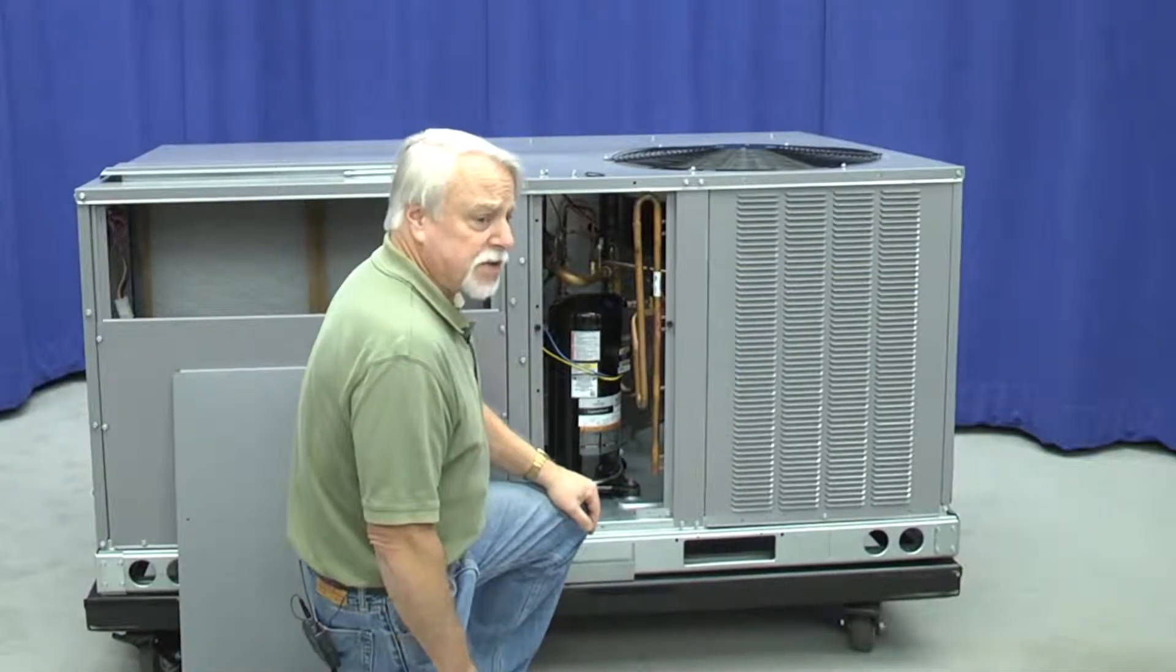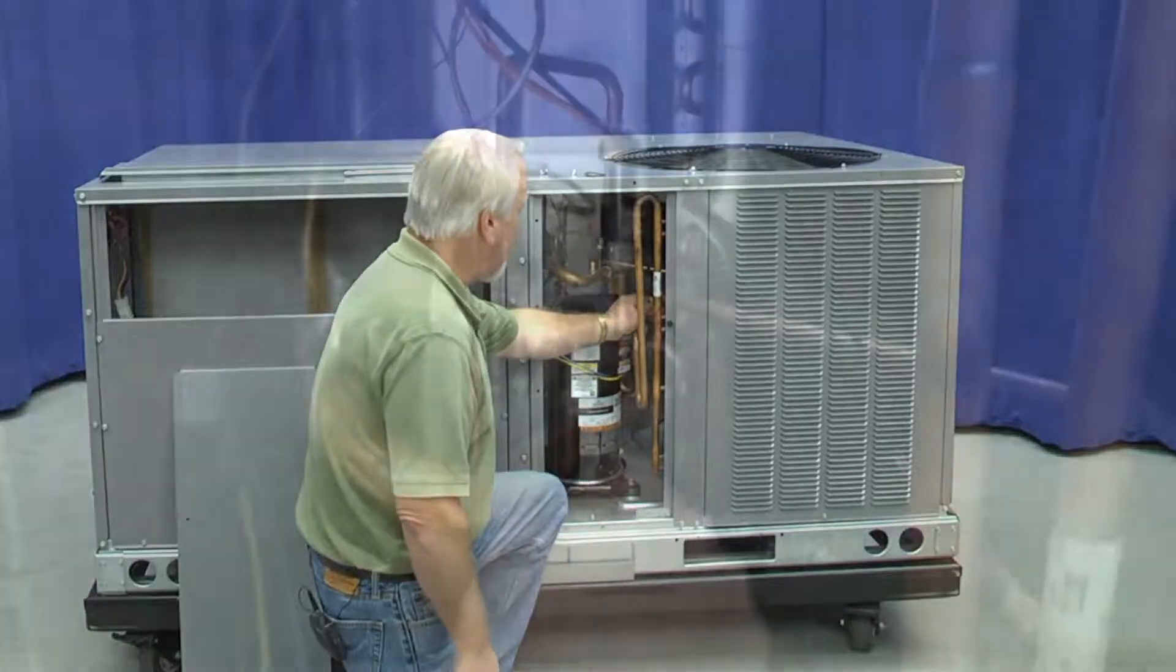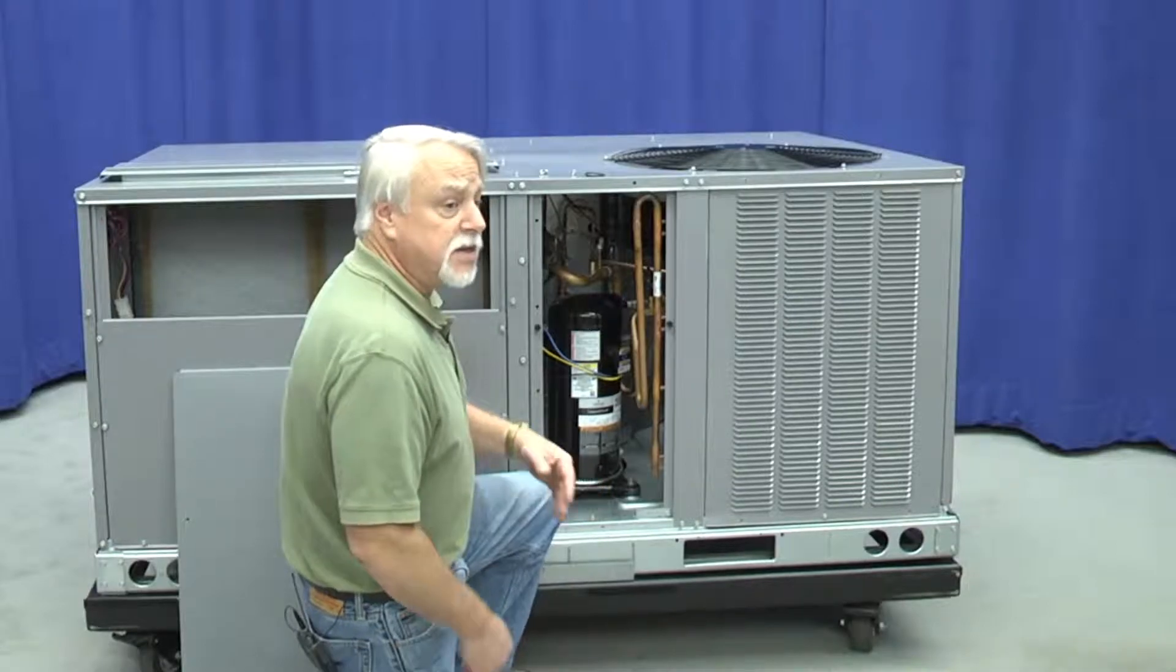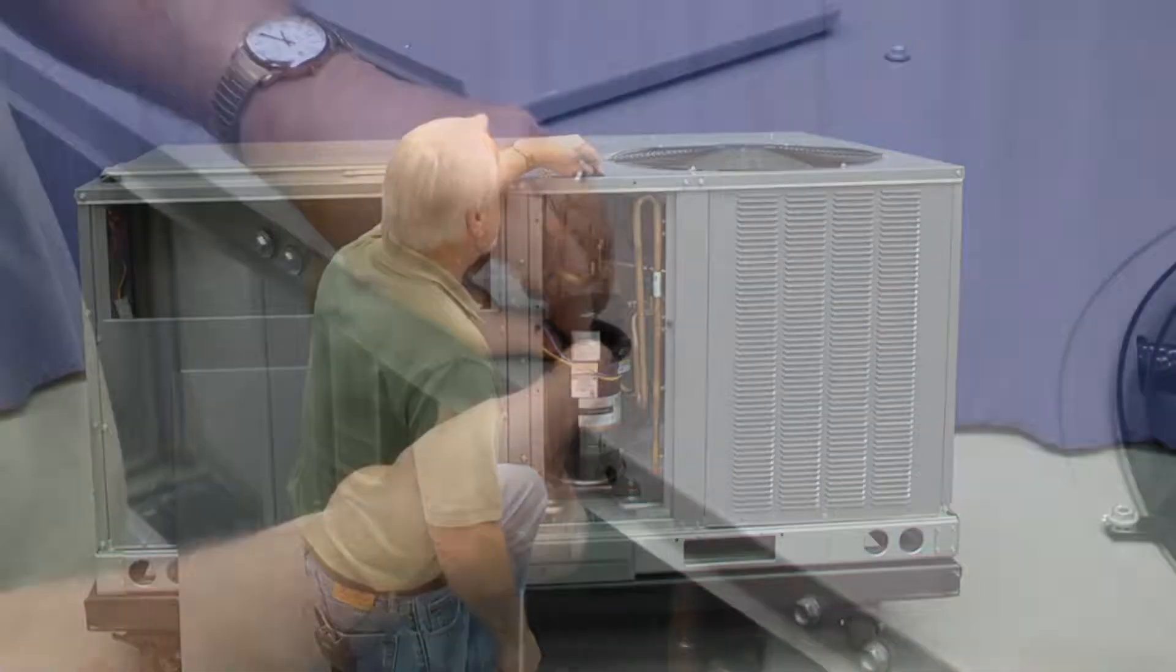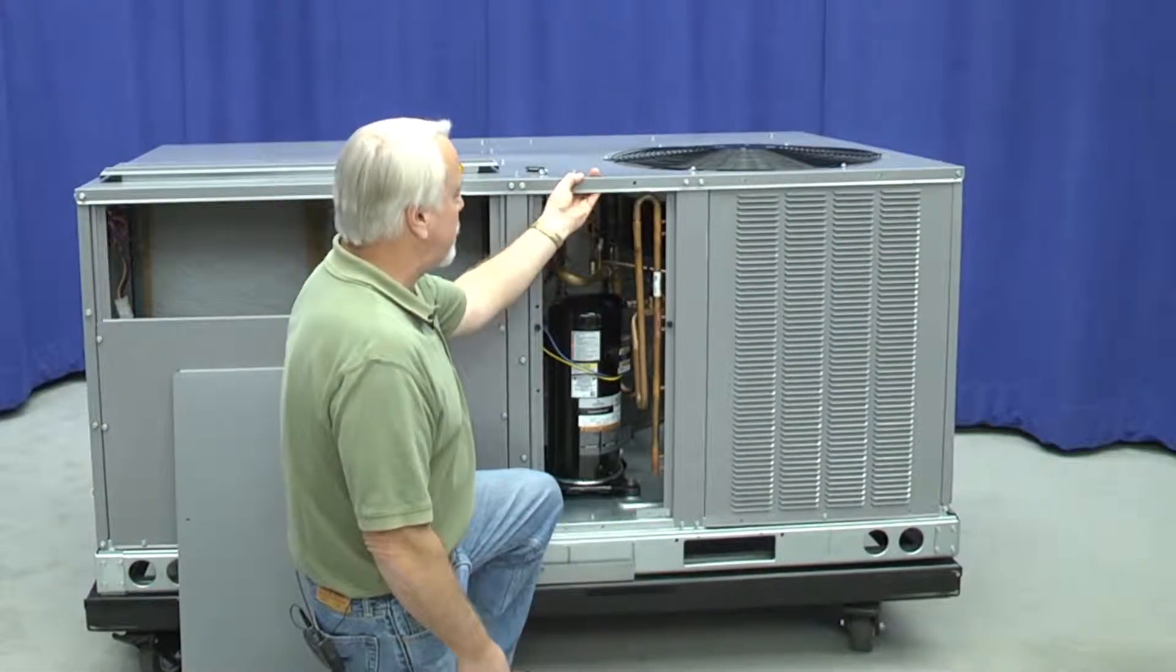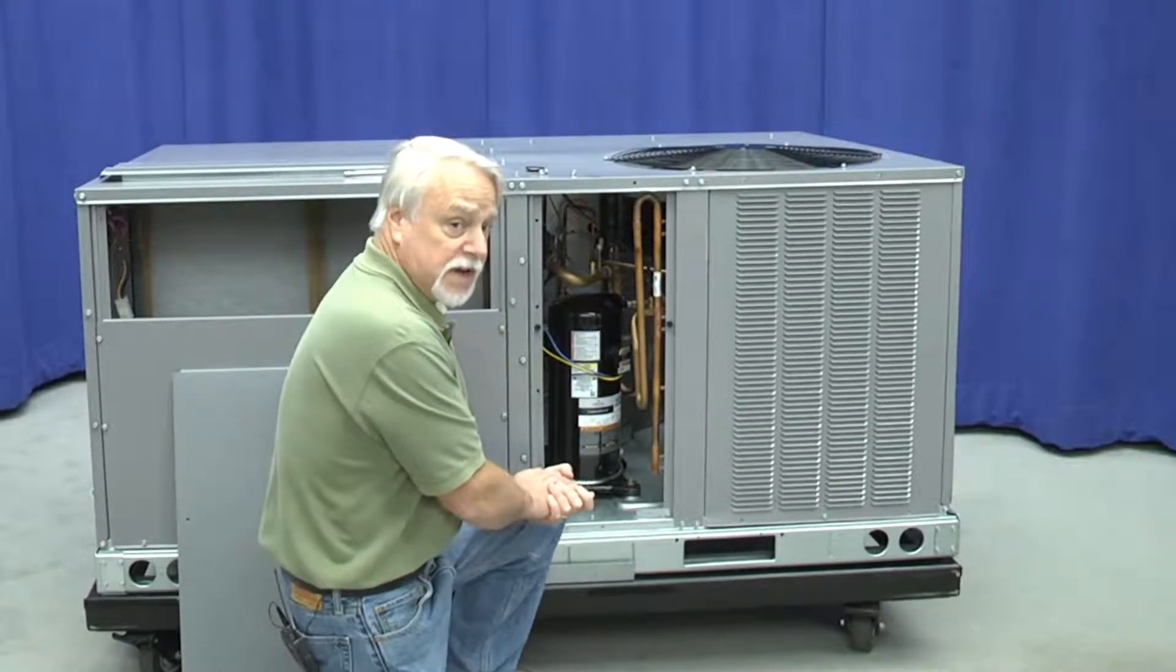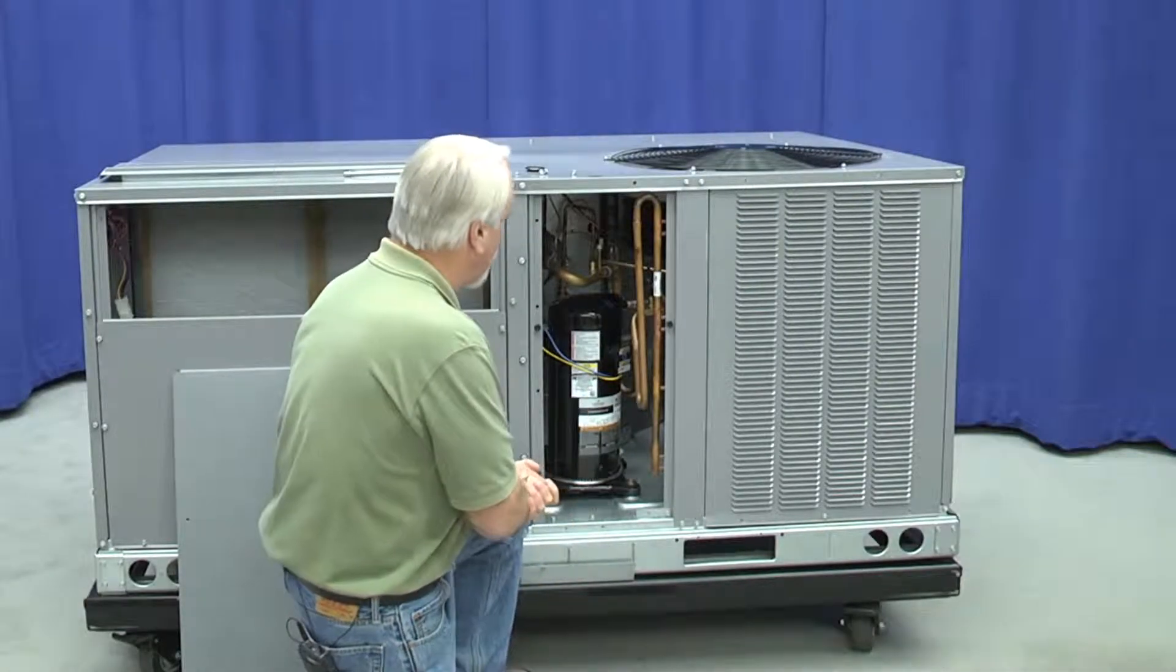With the compressor access panel removed, I can see connections up here for both my high side and my low side pressure, as well as liquid connections so I can check my refrigerant side pressure drop. By removing this plug in the top of the unit, I can route my gauge lines out through the top, replace the panel and then I prevent any bypass air over the condenser so I get a truer reading of how the refrigeration system is working.